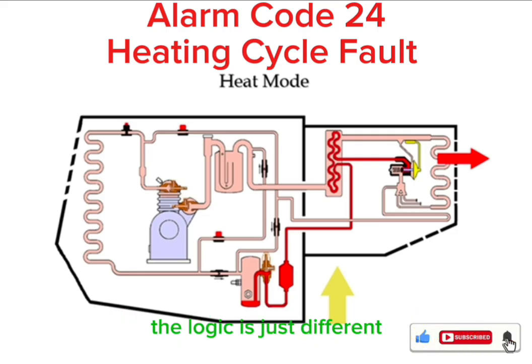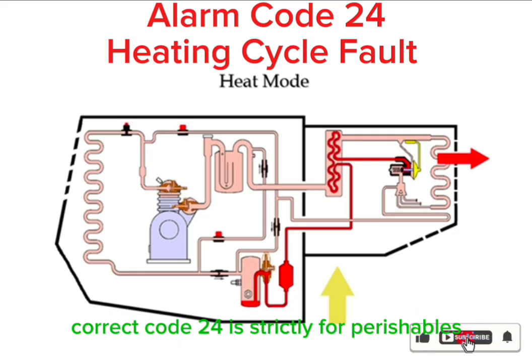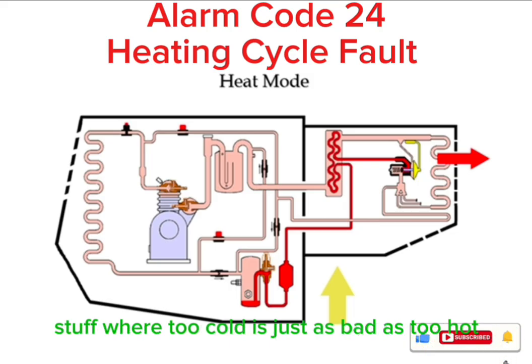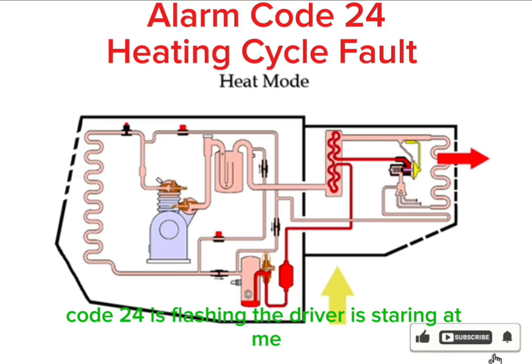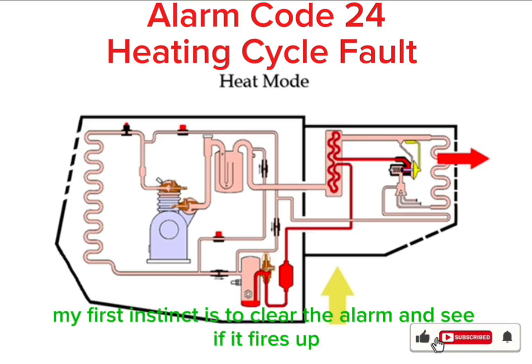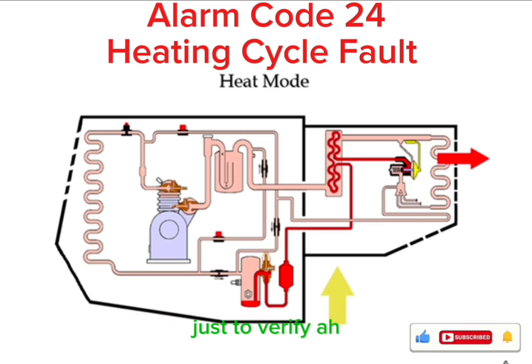The logic is just different. Correct. Code 24 is strictly for perishables, stuff where too cold is just as bad as too hot. Okay, so the unit is down, code 24 is flashing, the driver is staring at me. My first instinct is to clear the alarm and see if it fires up, just to verify. The clear and pray method. Yeah. Classic rookie move.